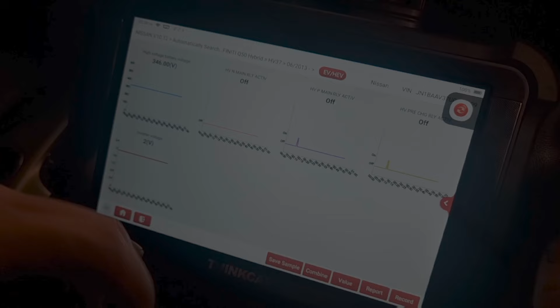So now what we need to confirm is whether that inverter voltage is actually low. Because technically the control module in that inverter could be faulty, and the voltage could be getting there, but it's just not seeing it. So what we need to do is clarify whether there is voltage getting to the inverter or not.